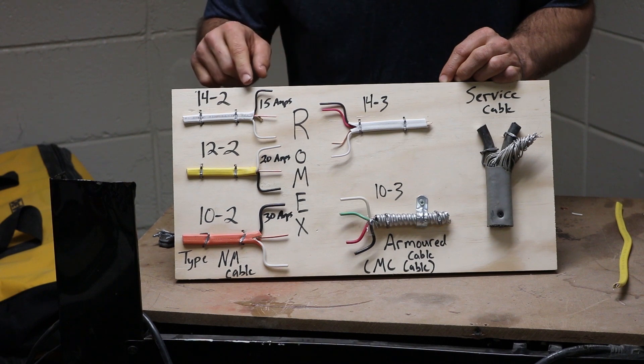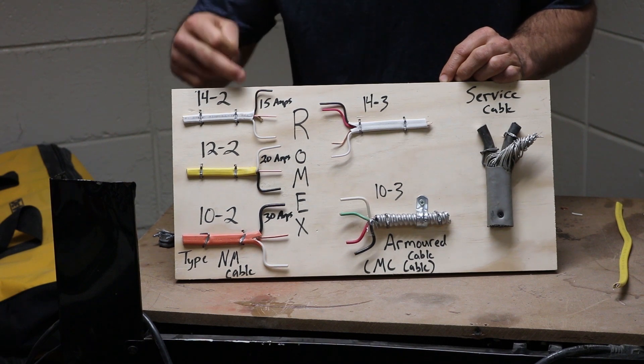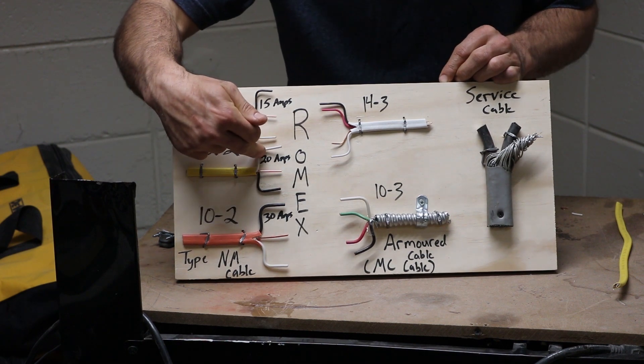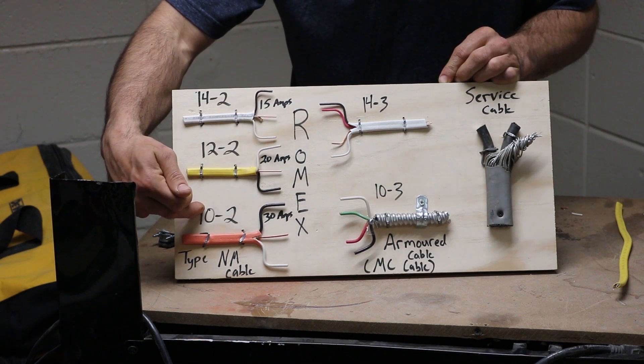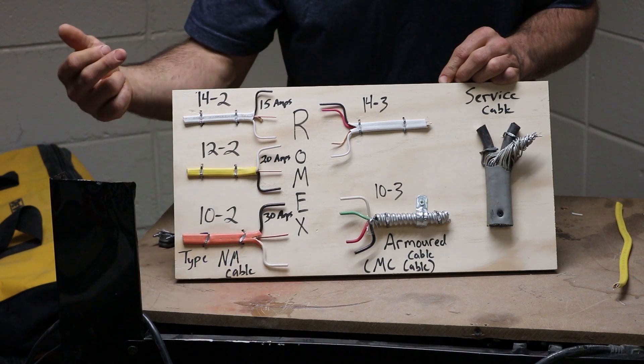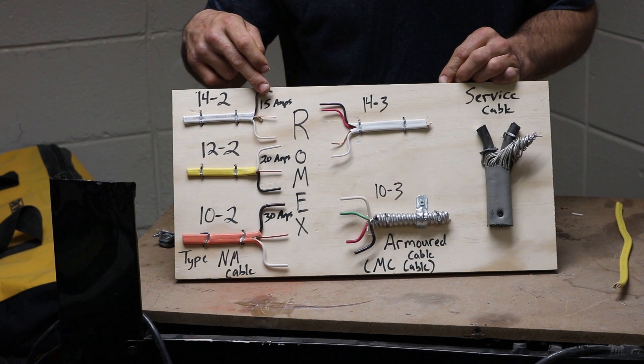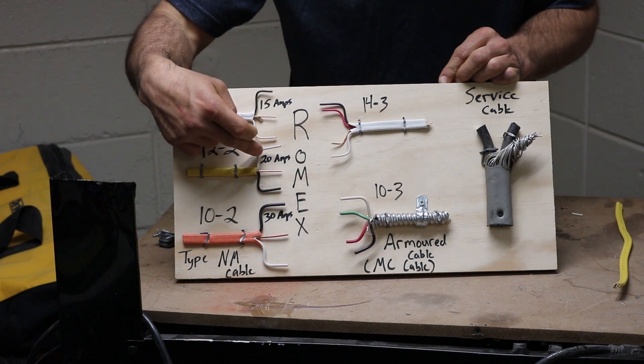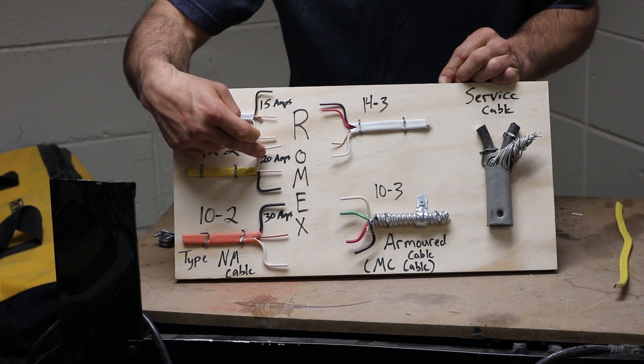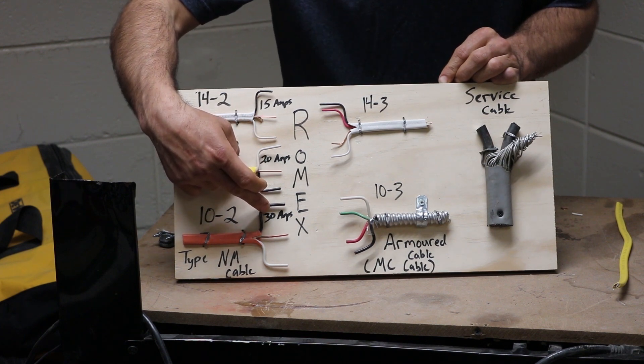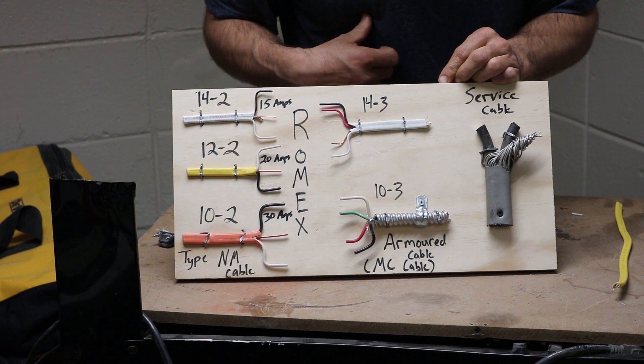Each wire can handle so many amps. A 14 gauge wire can handle 15 amps, a 12 gauge wire can handle 20 amps, and a 10 gauge wire can handle 30 amps. So if you were installing a lighting circuit, that'd be a 15 amp circuit. If you were installing maybe a kitchen appliance circuit, that would be a 20 amp circuit. And if you were installing maybe a dryer, then you would need a 30 amp circuit.